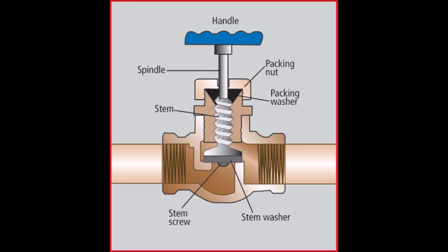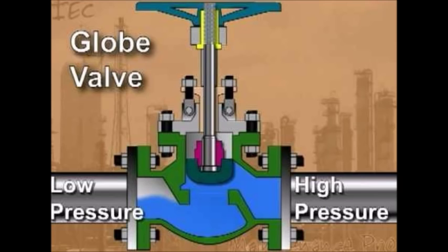Stem: The stem serves as a connector from the actuator to the inside of the valve and transmits this actuation force. Stems are either smooth for actuator controlled valves or threaded for manual valves. The smooth stems are surrounded by packing material to prevent leaking material from the valve. This packing is a wearable material and will have to be replaced during maintenance.